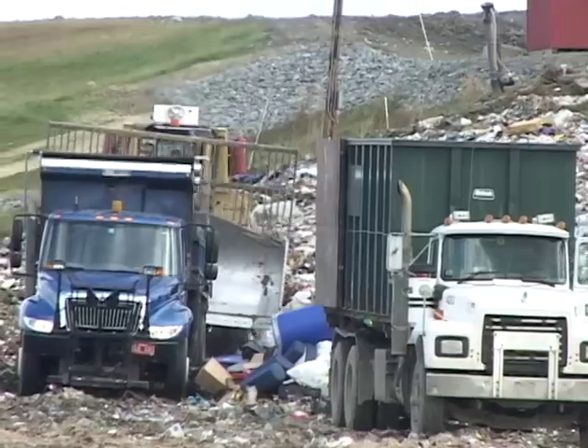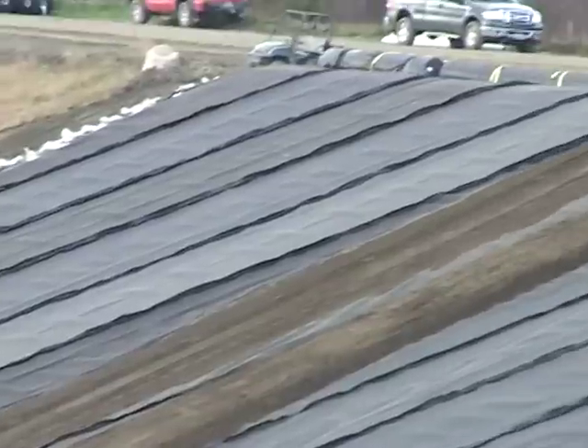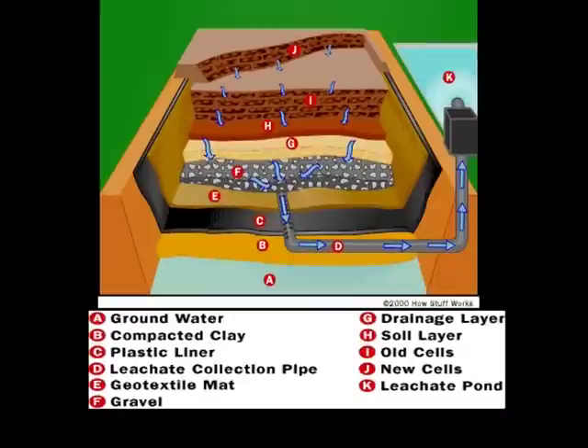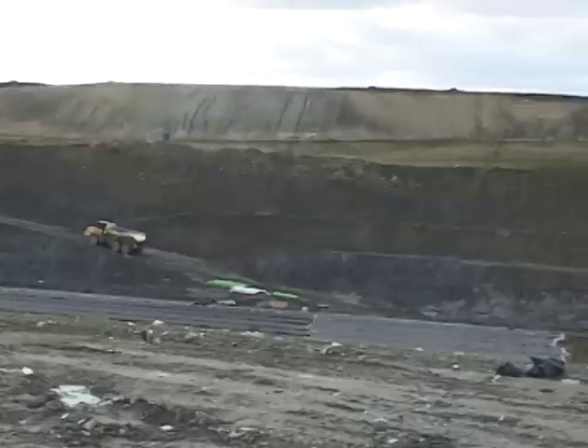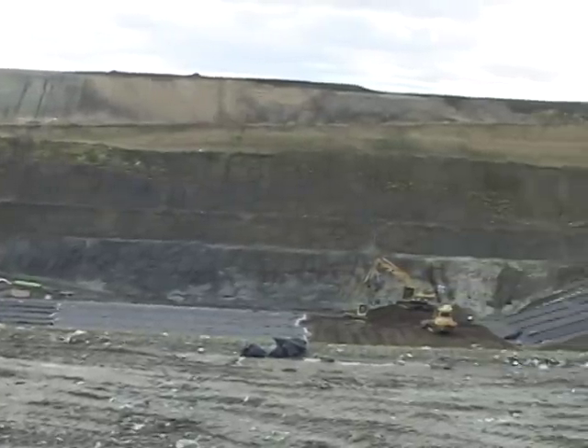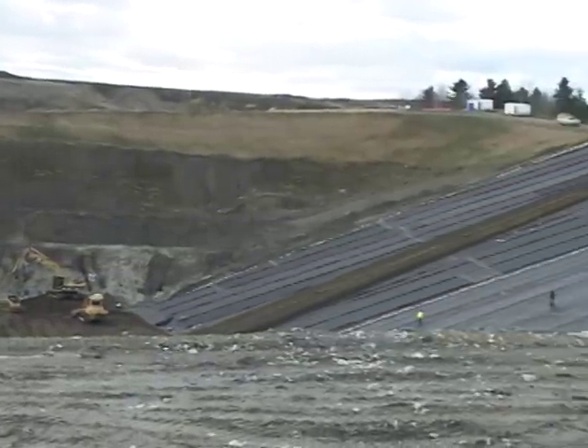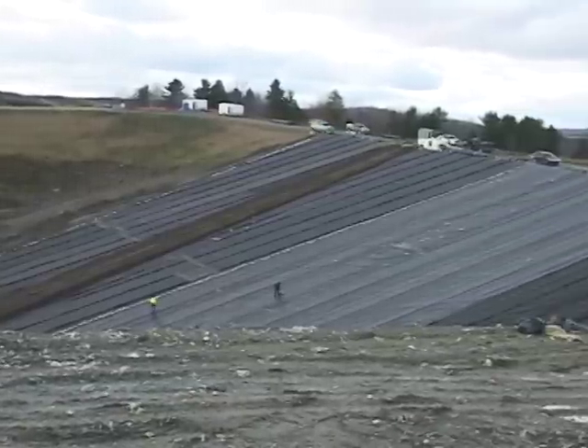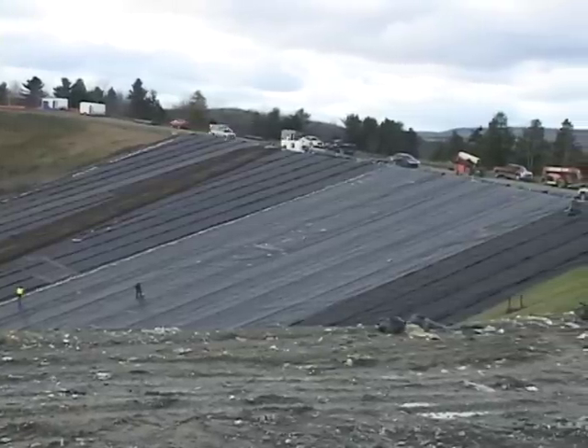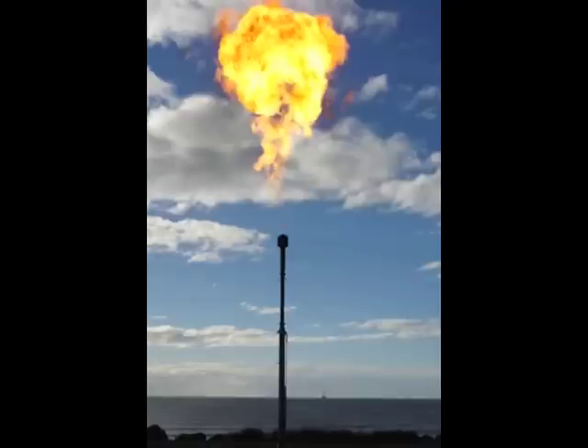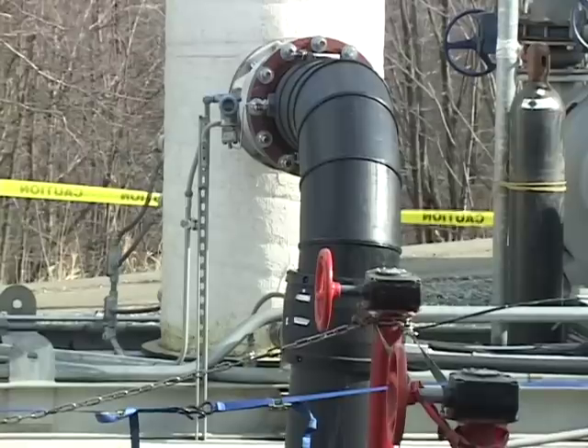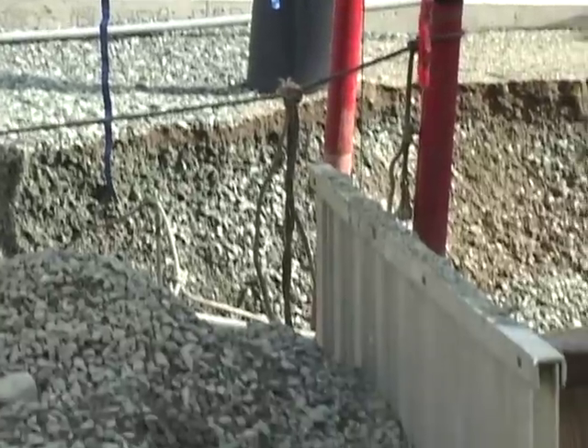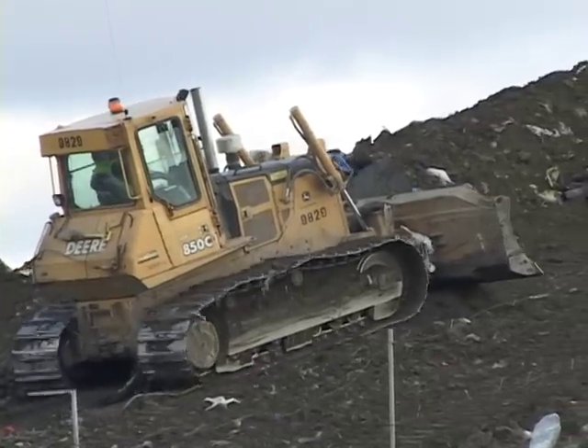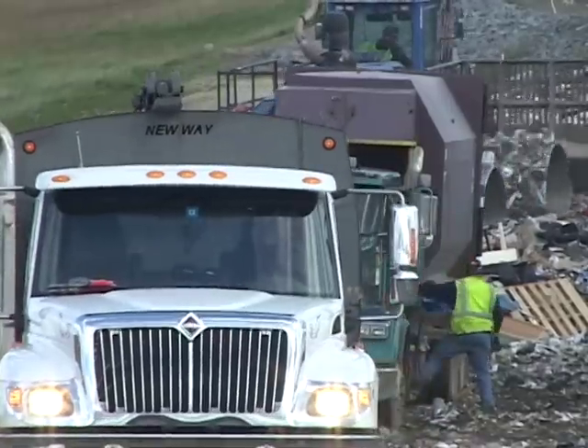So a modern operating landfill has to collect the methane and burn it. As the landfill is filled in cells, they construct the gas collection system as they fill in the trash around it. Any landfill has to collect that gas to get their air quality permits, and they have to burn it. If you're not generating electricity, you'd drive by a landfill like the Moortown landfill until recently and see a big pipe sticking out of the ground, and especially at night, huge flames. All we're doing, to boil it down, is taking that pipe and sticking it in here to do something useful with the gas first. That's why it's considered renewable, and it's really not a whole lot more complicated than that.